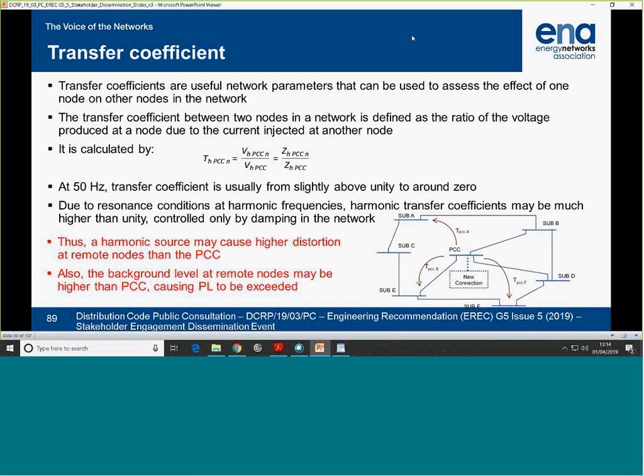And this simple equation here tells you the transfer coefficient. It is the ratio of the transfer impedance, which some software calls mutual impedance, to the self-impedance at the point of connection. So basically, in order to do this, I need to tell my software, my model, to give me the self-impedance at this point, or the Thevenin equivalent at this point, and the transfer impedance at other nodes. And really all the software, PowerFactory and other software, easily gives you that.